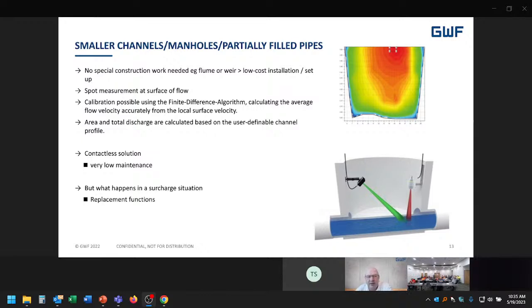By doing this, we don't need any kind of special construction work, we don't need a flume, we don't need a weir, so it's a very low installation cost for the setup. And because we know that no channels are the same, many of the vendors out there allow for a user-definable channel profile. So some of the things that are good here: it's contactless, it's very low maintenance, you're not having to clean a sensor, but at the same time we're having to correct for the fact that we're taking a spot measurement.